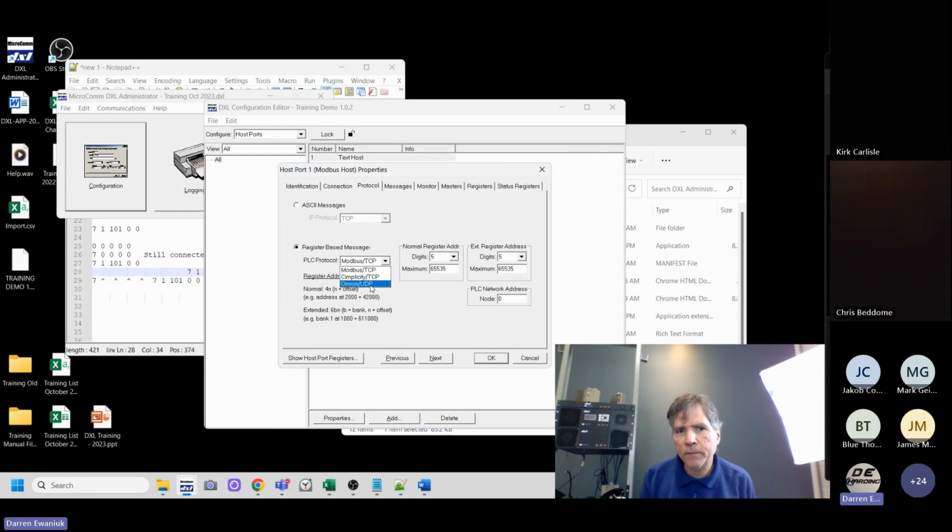Modbus, particularly for the data acquisition servers, a lot of them don't allow you to write values into it. It only does reads and writes itself. So Modbus normally is polled only. Omron is normally peer-to-peer only. Simplicity is a variation of Modbus that you can write values, so it's peer-to-peer Modbus for the Simplicity software. So I'm going to use Modbus.